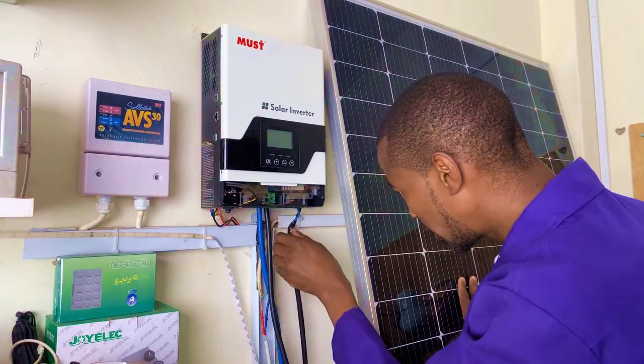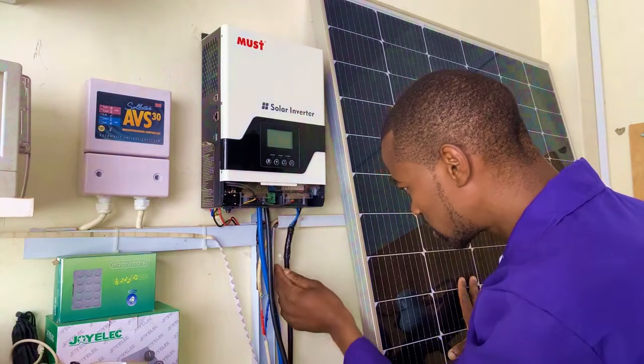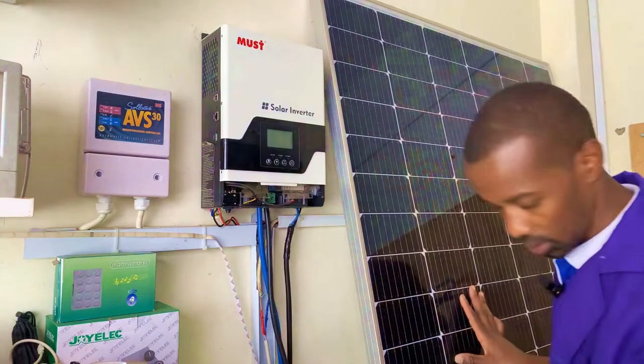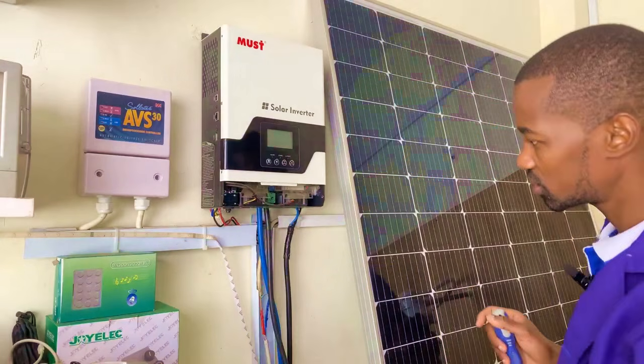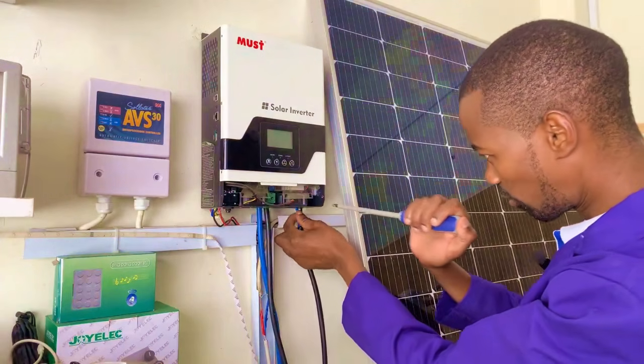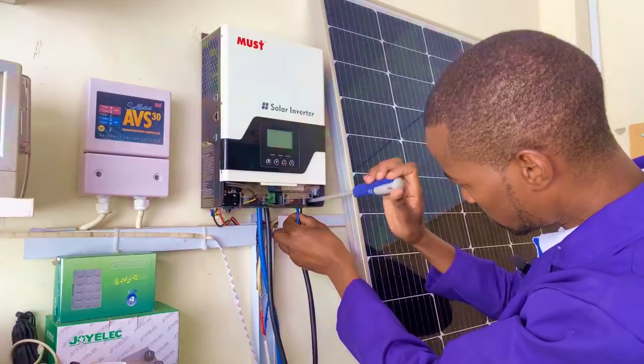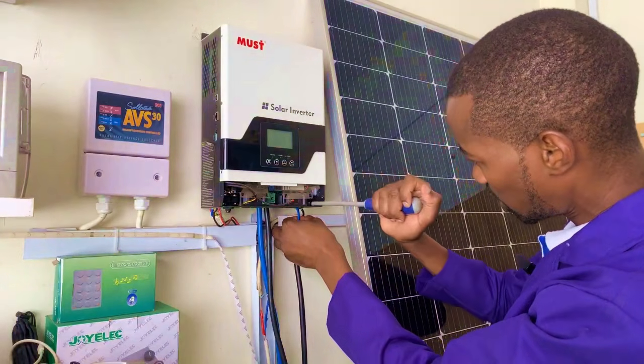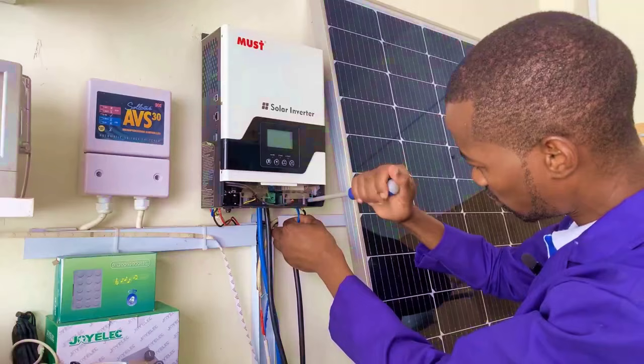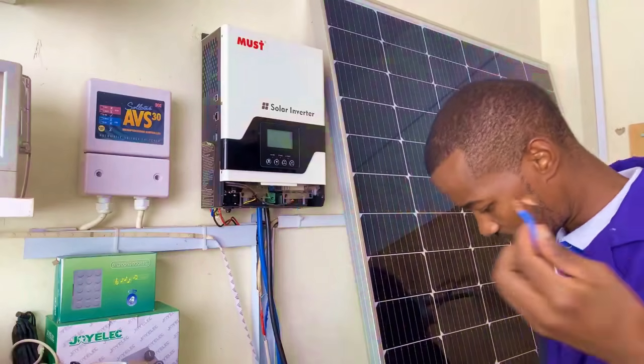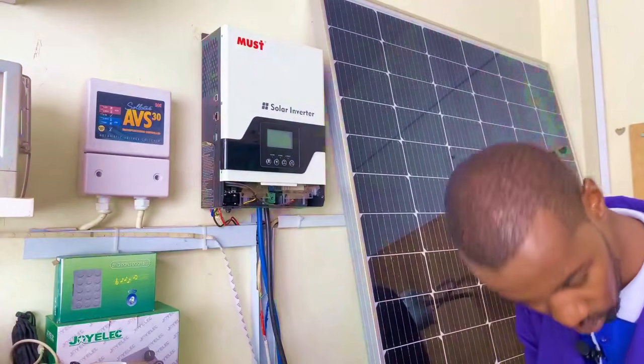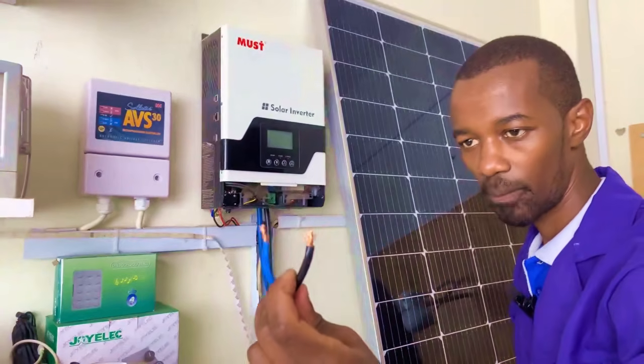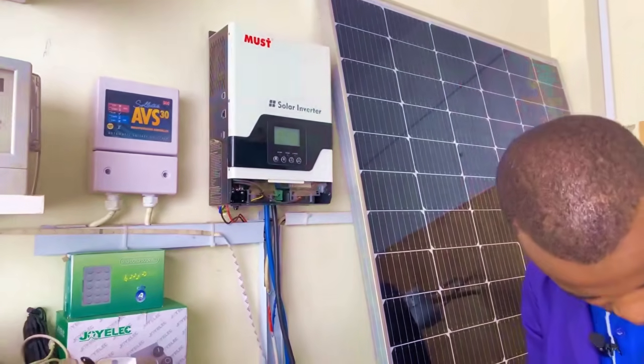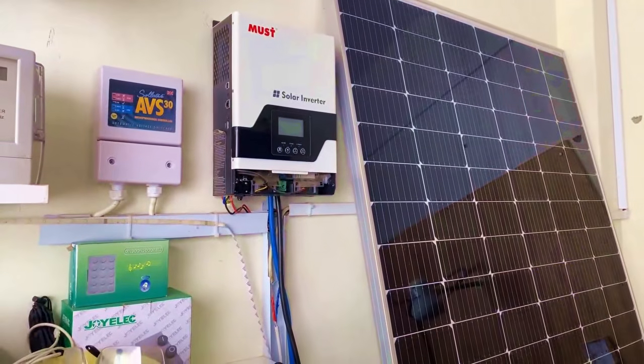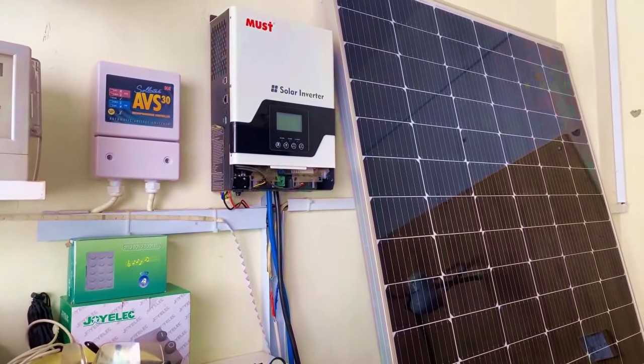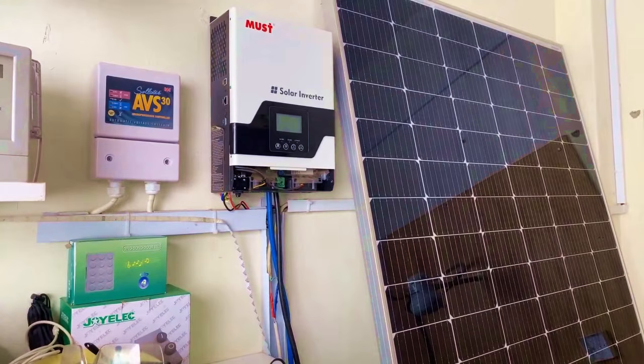When disconnecting an inverter from a battery, you start by disconnecting the PV, which is why our PV is off. We disconnect the PV, which stands for photovoltaic, in other words solar. Look at the cables we have for PV. Let's make sure we disconnect it completely from the inverter.